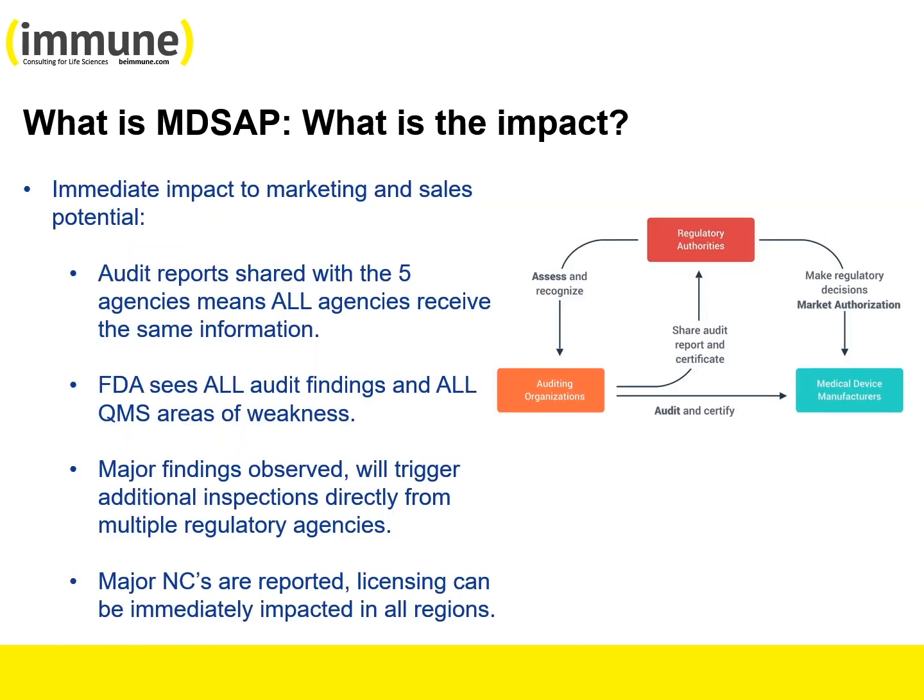So just what are the impacts of MDSAP certification? Well, some of the positive impacts are that it can allow you to enter a market. For example, in Canada, you are not allowed to market your product unless you have MDSAP certification as a foreign manufacturer. There can also be some negative implications if you have nonconformities which potentially compromise the quality of your products in the marketplace. The immediate impact to marketing and sales is that these audit reports are shared with all 5 participating agencies. This means that they all receive the same information.